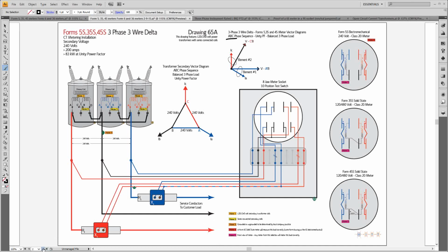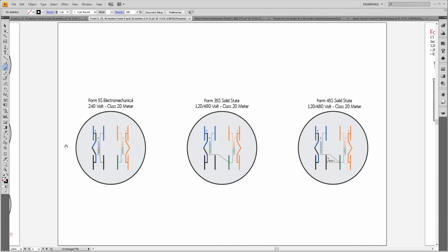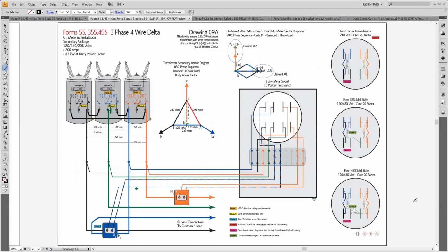So now we're going to look at 3-phase 4-wire delta with the same meters. 3-phase 4-wire delta, when we do it with a 2-element meter, we're not doing Blondels. With the 3-phase 3-wire delta and a 5S, 35S, or 45S, any one of those are Blondels, but this is not going to be Blondels. We're tricking Blondels by making the connection we're going to make. And so the same setup, the meters are no different, same exact metering. I've changed all the colors to match the drawing for the 4-wire delta. And so we'll go to the drawing for the 4-wire delta so we can see what is happening in the 4-wire delta with 2 CTs.